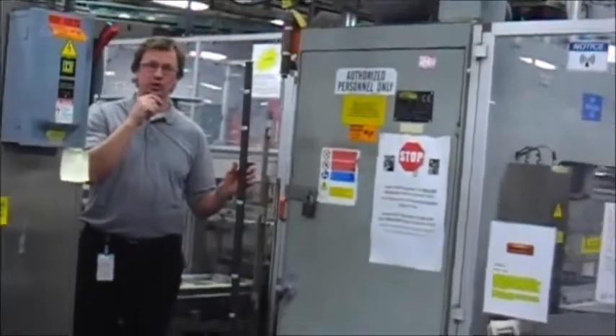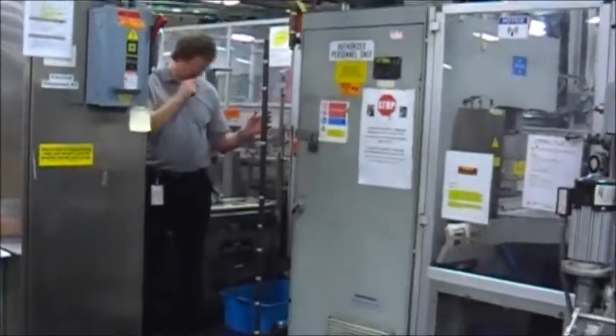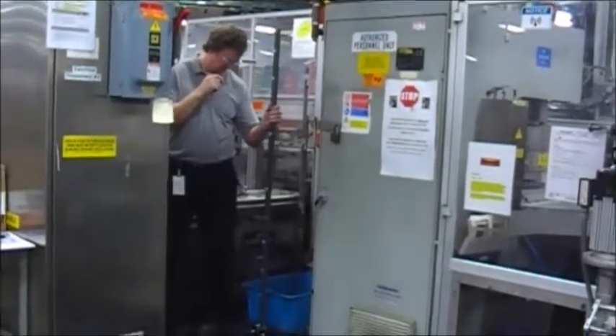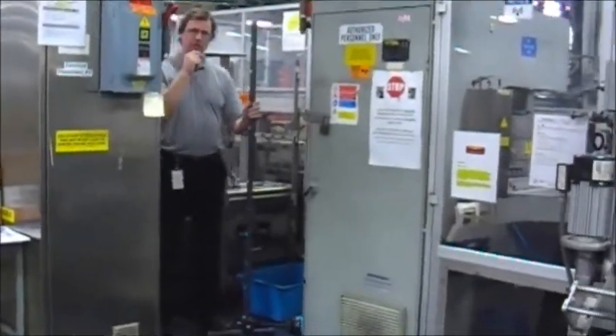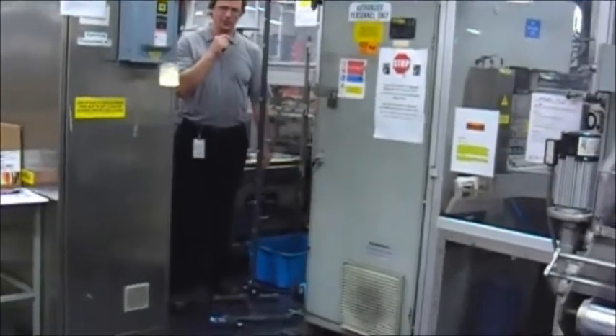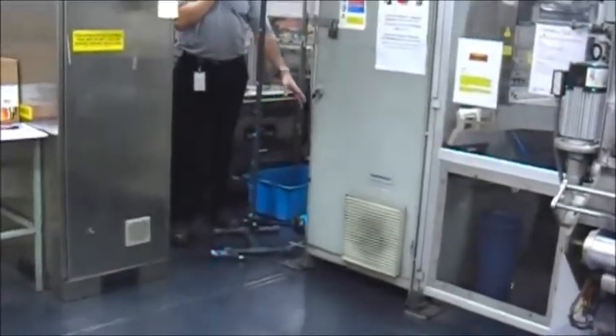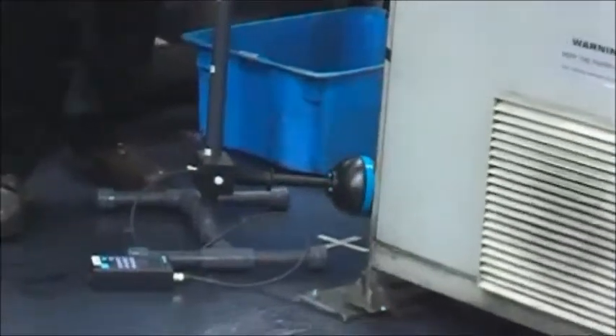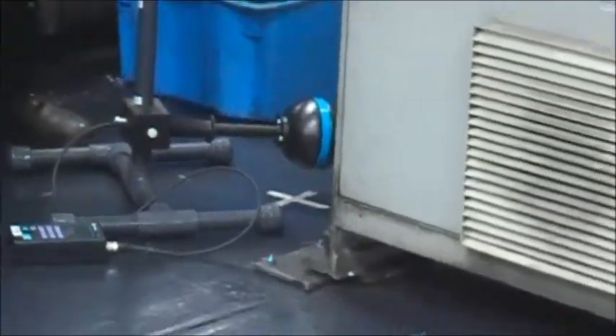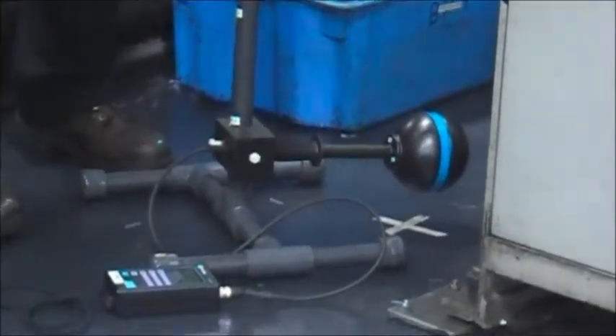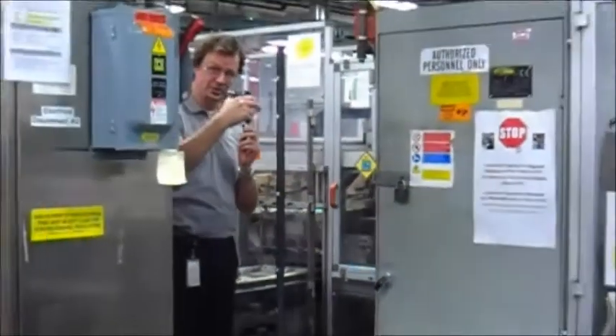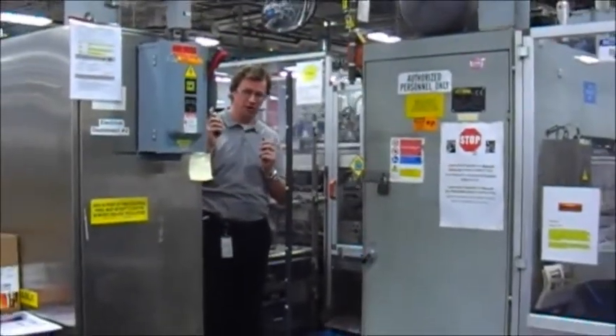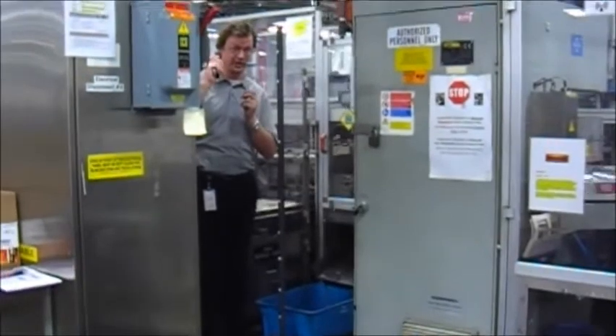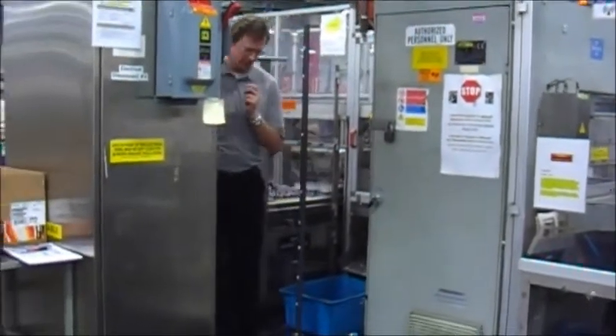Next, we'd like to demonstrate proper measuring techniques for RF. First, I want to make sure the stickman and the probe are in the proper position. In this case, we are 6 inches from the guarding. We've got our probe horizontal. Before I take measurements, I want to make sure that I remove the cell phone. Any cell phones or fluorescent lamps that are close by will interfere with your RF signals and either artificially inflate or artificially lower your measurements.